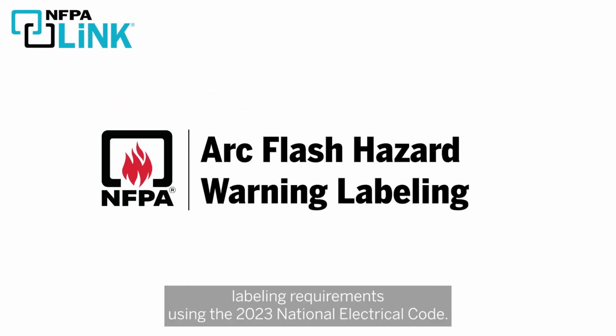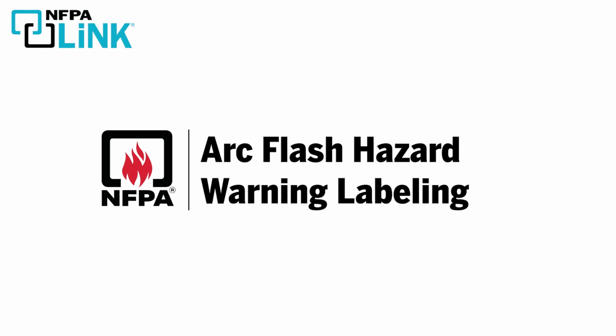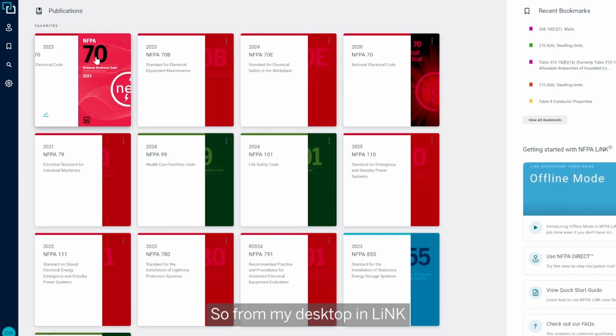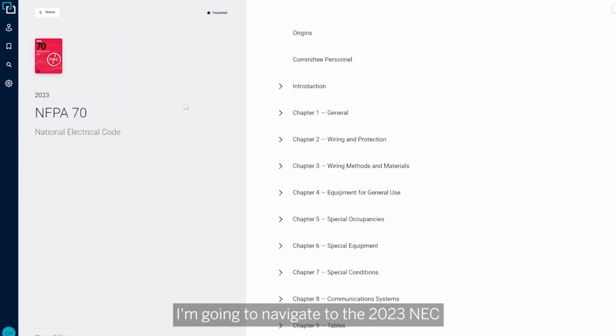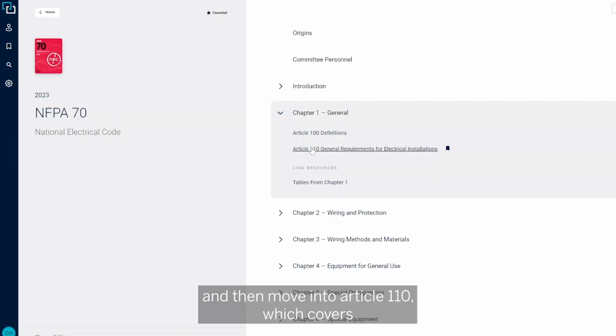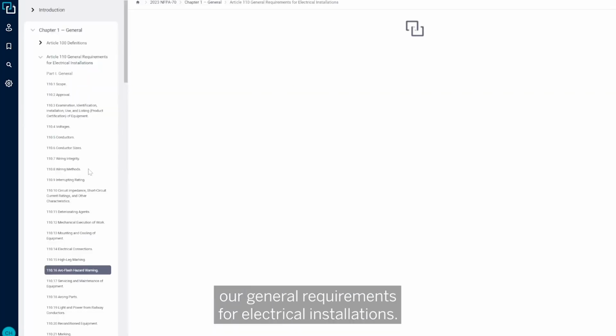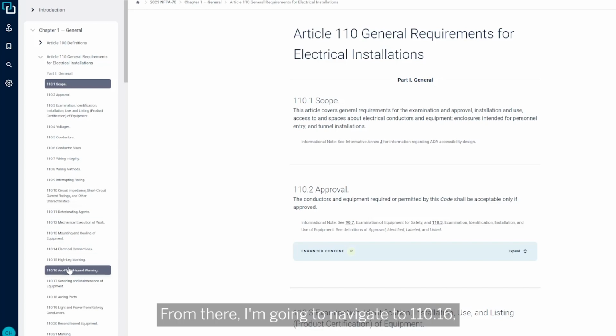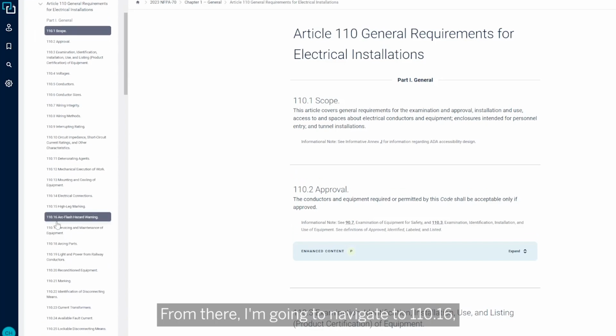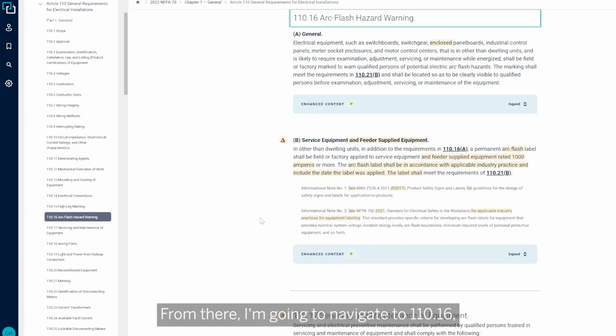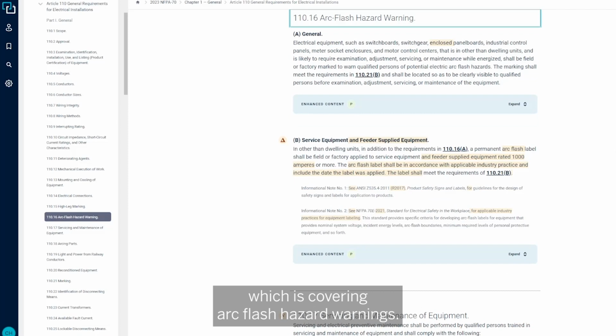Today, we've been asked to address arc flash hazard warning labeling requirements using the 2023 National Electrical Code. So from my desktop in LiNK, I'm going to navigate to the 2023 NEC and then move into Article 110, which covers our general requirements for electrical installations. From there, I'm going to navigate to 110.16, which is covering arc flash hazard warnings.